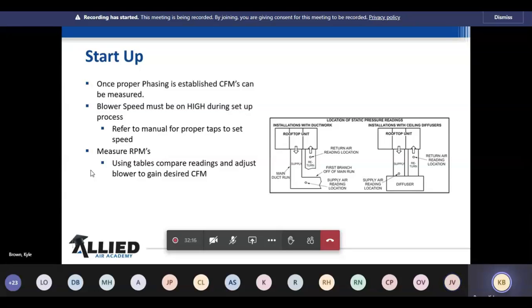You could put two ports right there and get your pressure reading and stuff of that nature. Make sure we do this and get it right, because next week we're going to go into tacking motors and things like that to find CFMs. And if you have an air balancing company that comes in and does it, you'd probably be well served talking to that company or knowing that company very well to know where they take these readings. If they do not take these readings in the correct spot and there's something in there that can make a difference, that's something you need to know, and you can help them correct it.